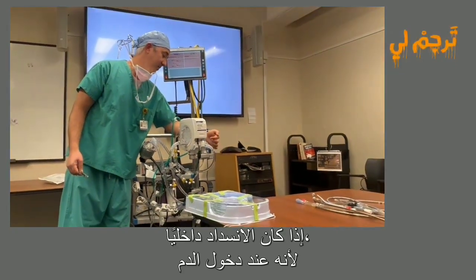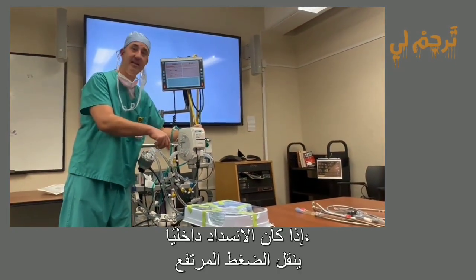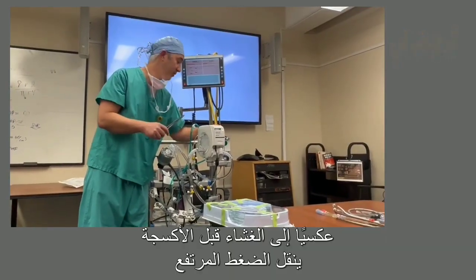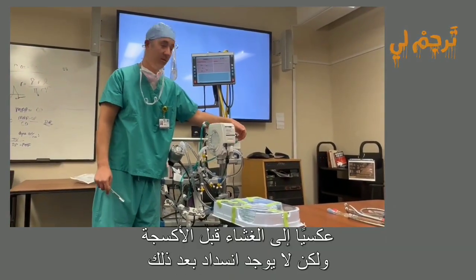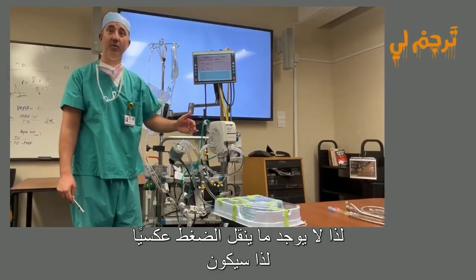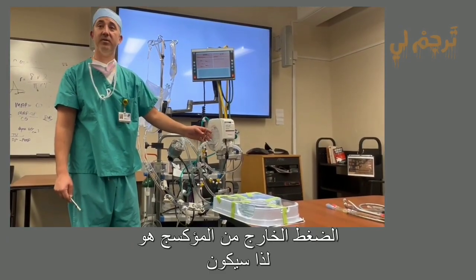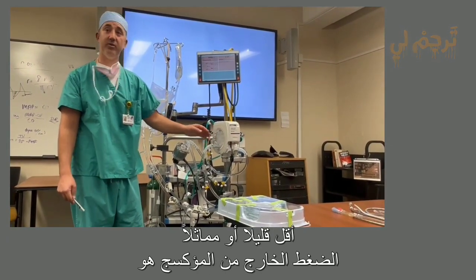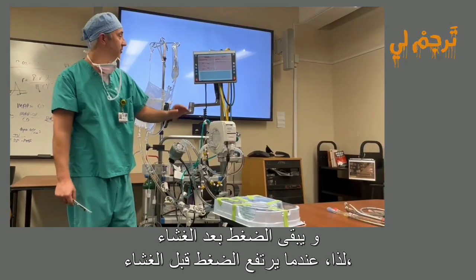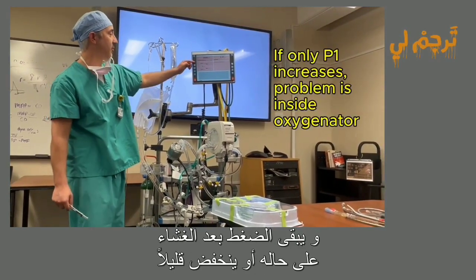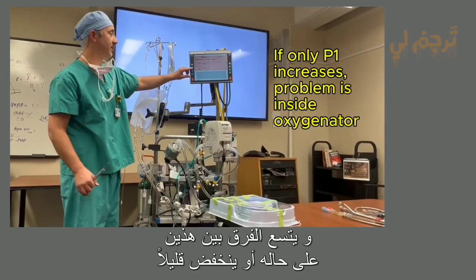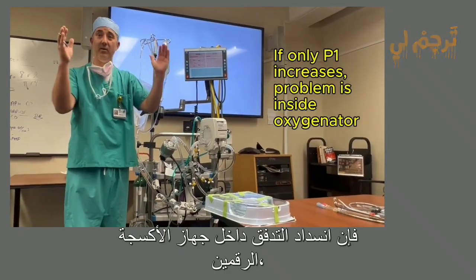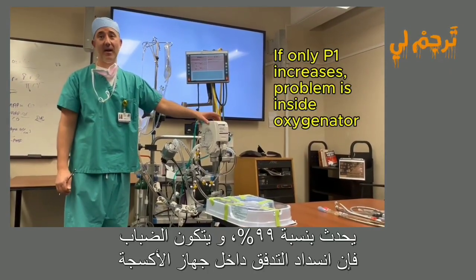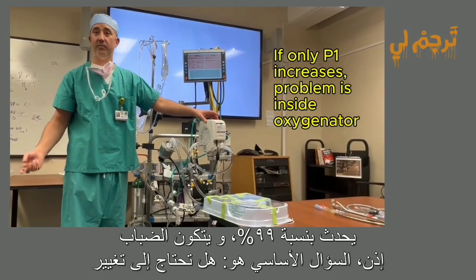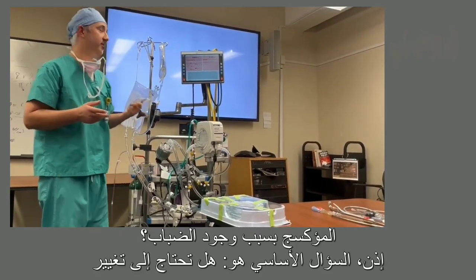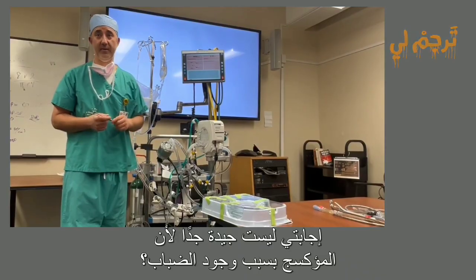Because as the blood goes in, if the obstruction is inside, the transmission of higher pressure goes backwards to the premembrane, but there's nothing obstructing afterwards. So there's nothing to transmit the pressure backwards. So the pressure coming out of the oxygenator is going to be a little bit lower or the same. So when the premembrane pressure goes up and the postmembrane pressure stays the same or goes a little bit down, and the difference between those two numbers gets wider, that is obstruction of flow inside the oxygenator. 99% of the time it's clogged. So the basic question then is, do you need to change the oxygenator because it's clogged?